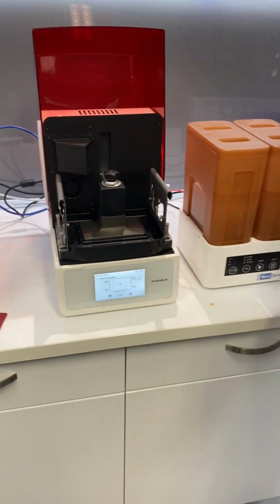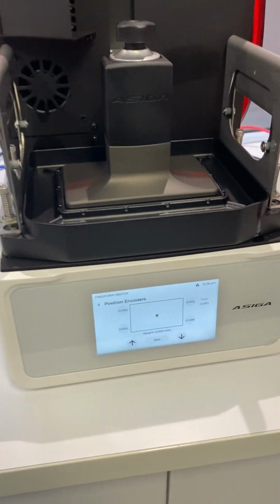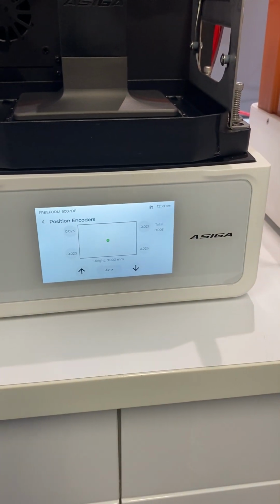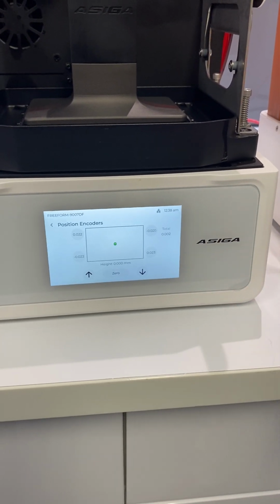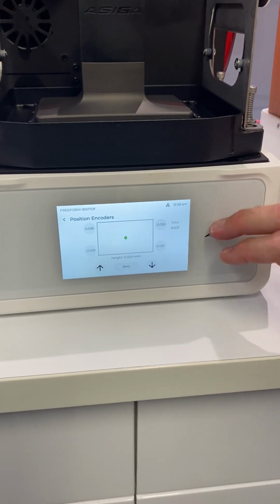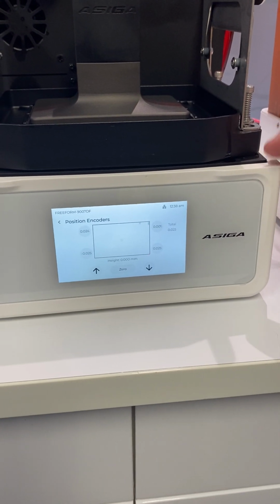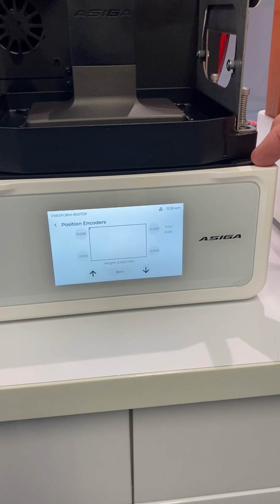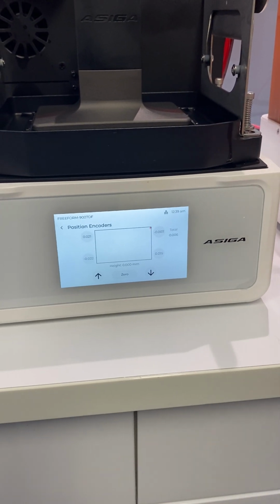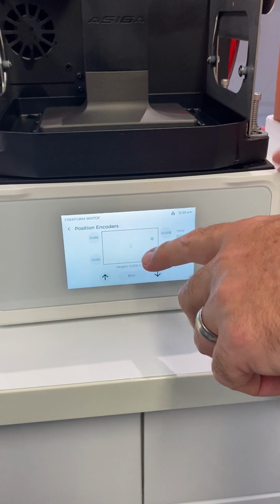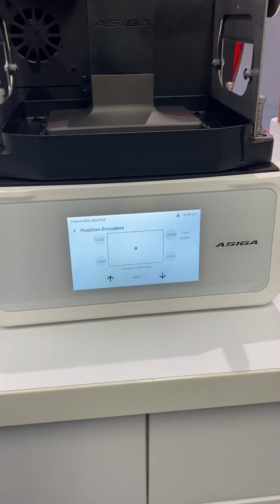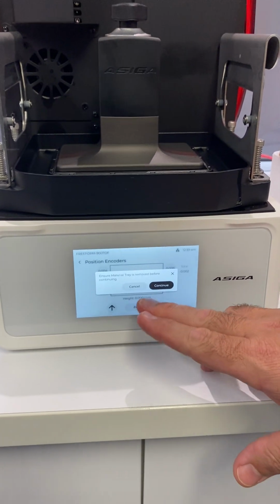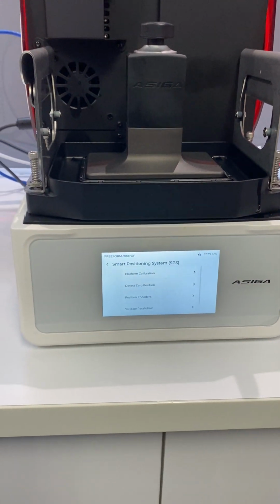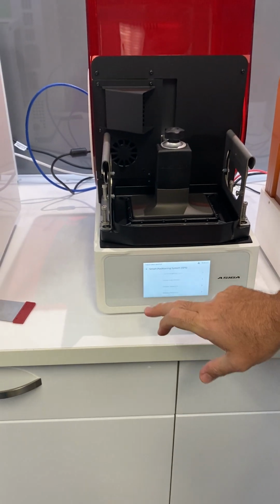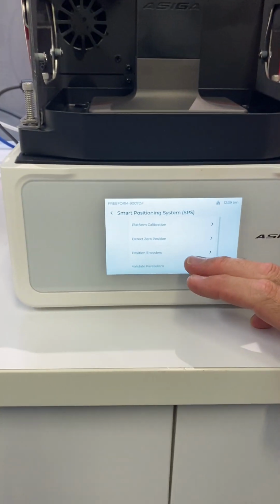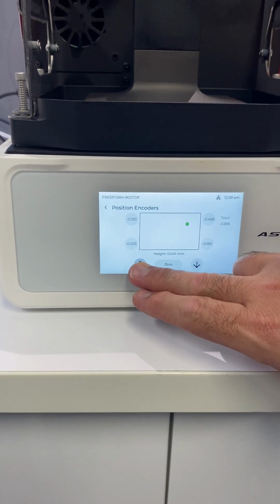Now, this little green dot, we don't have any issues on the Max 2s, but on the original Maxes, with the connection and the position encoders, sometimes a USB stick needs to just come out or in. But essentially, if you've got any vibrations or the position encoders are giving feedback that there's vibration, it will also give you a 300 cannot approach, approach fail error in 300 seconds. So yeah, we'll just take this back up again.